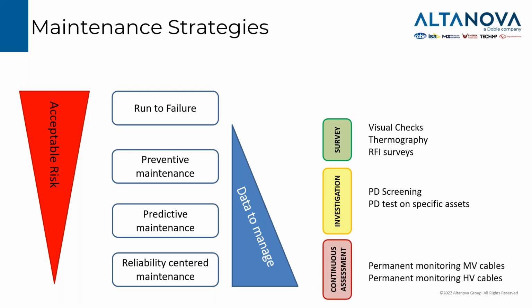In the end, if we want to move to a fully complete system that gives us the highest quality and quantity of information to be used to decide our maintenance strategy, we can move to continuous assessment. So we can have permanent monitoring of medium voltage cables, or as well for high voltage cables. There are a few differences that will be described in the next slides.